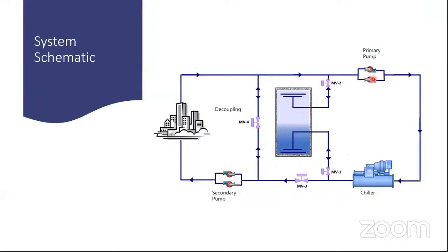So the primary will suck as much as it has to, depending upon its capacity. Any surplus water that was drawn from here will come back to this. So this is the warm water that is coming back. The mixing of this warm water should not happen inside the thermal storage tank. So for that only these top and bottom diffusers are used in a stratified tank.